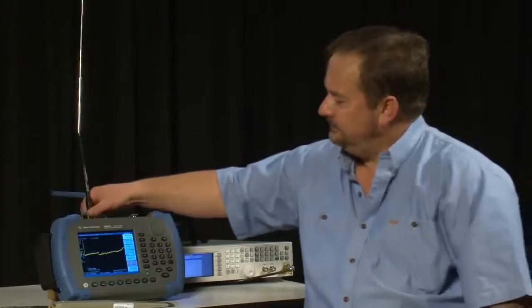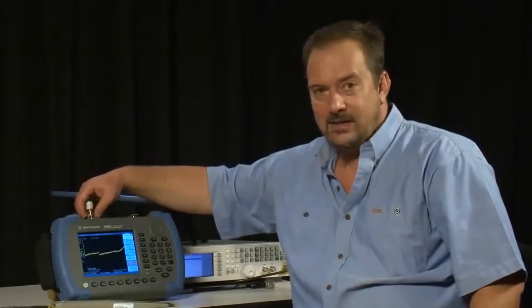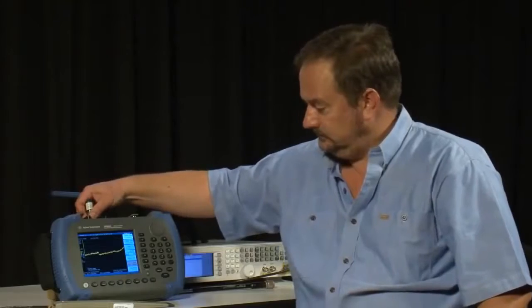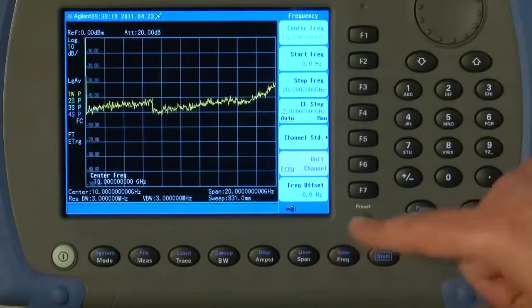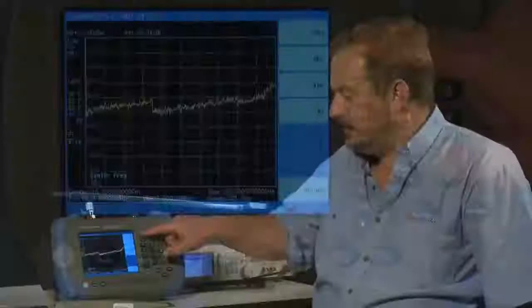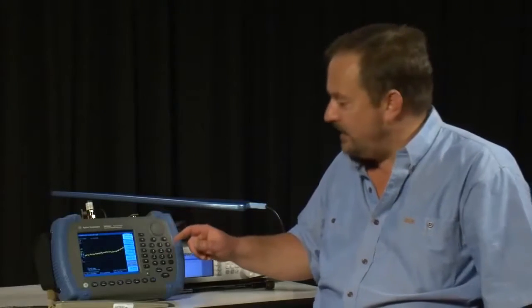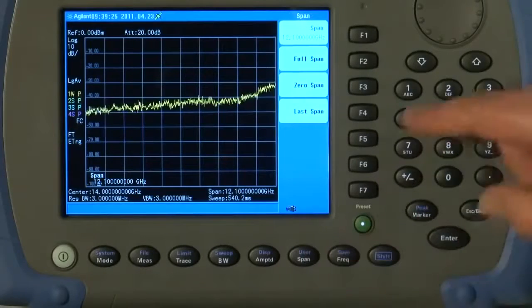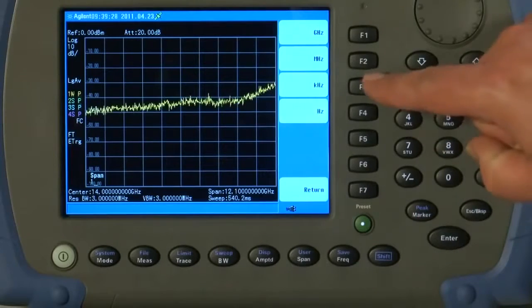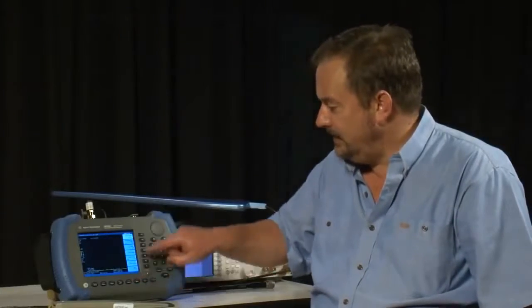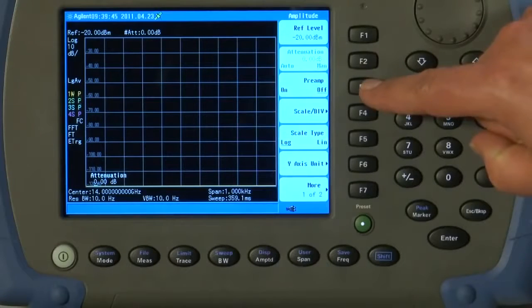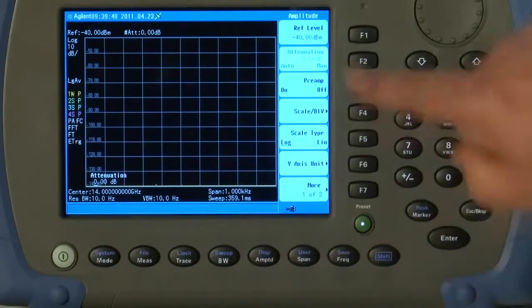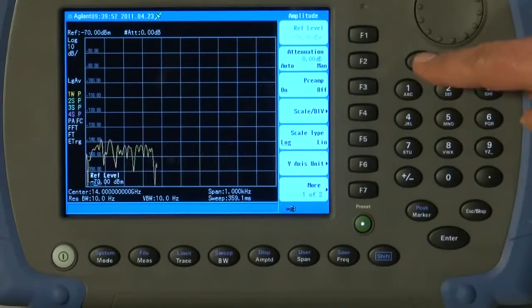So, I will disconnect the antenna and connect a 50 ohm termination to the input. I will press Instrument Preset and select a frequency of, say, 14 GHz, which is a common frequency used in digital microwave links. I will set a span of 1 kHz, and let us press the Amplitude button. We will set the attenuation to 0 dB, turn the pre-amplifier on, and adjust the reference level to bring the trace back up onto the screen.